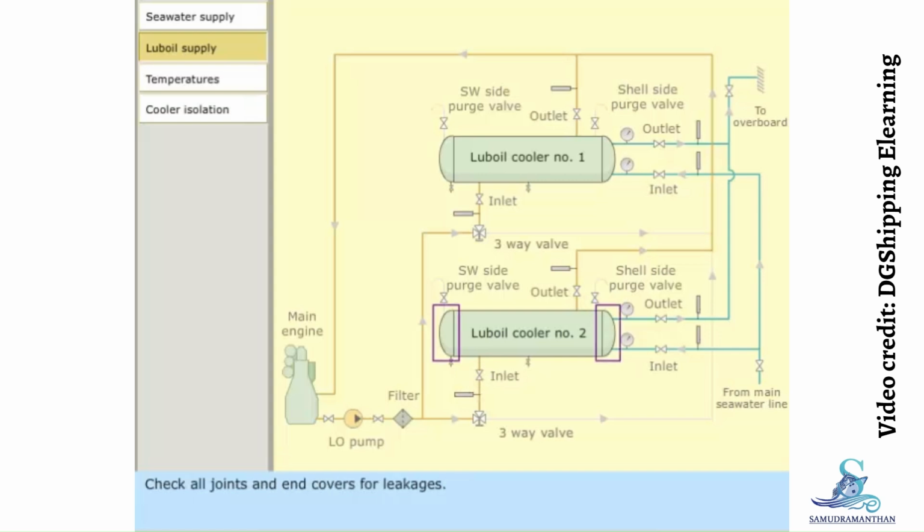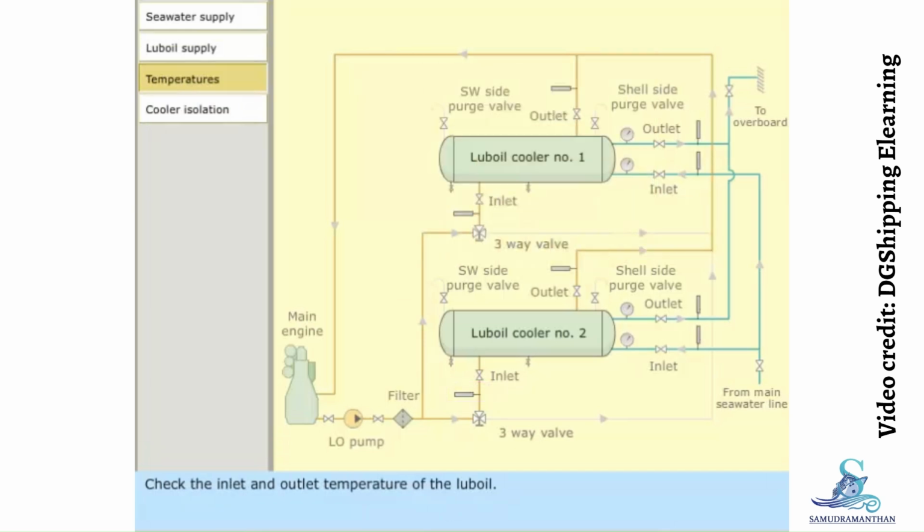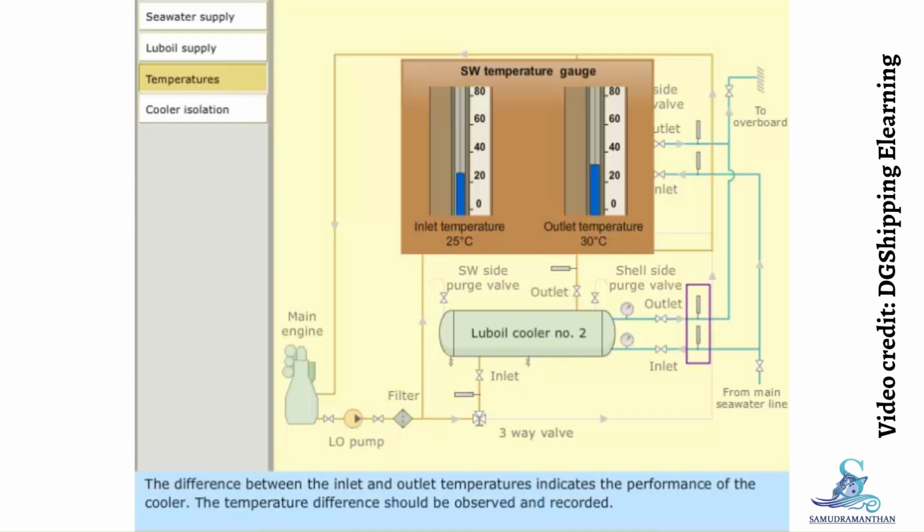Check all joints and end covers for leakages. Check the inlet and outlet temperature of the lube oil. Check the inlet and outlet temperature of the seawater. The difference between the inlet and outlet temperatures indicates the performance of the cooler. The temperature difference should be observed and recorded.